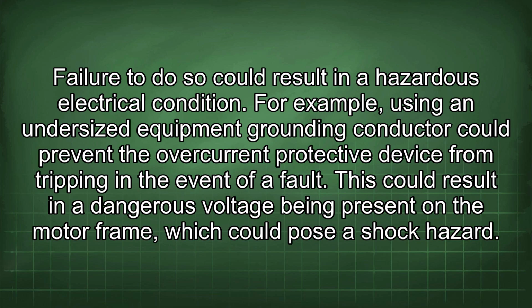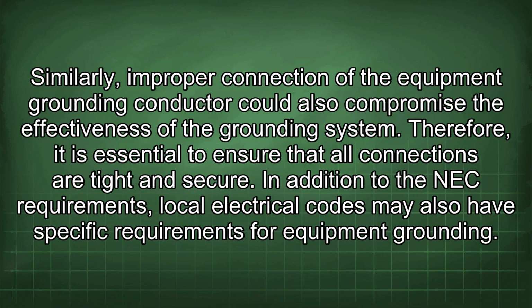This could result in a dangerous voltage being present on the motor frame, which could pose a shock hazard. Similarly, improper connection of the equipment grounding conductor could also compromise the effectiveness of the grounding system. Therefore, it is essential to ensure that all connections are tight and secure.